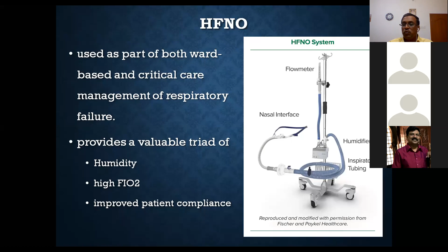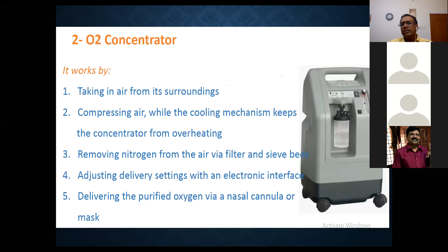This is an oxygen concentrator, not commonly used nowadays here, but it doesn't need any oxygen source. The oxygen source is the environment. It's taking air from the surroundings and compressing the air, and cooling mechanisms keep the concentrator from overheating, and it removes the nitrogen via filter sieve beds present here, thereby adjusting the delivery settings, and they can increase the concentration of oxygen that can be delivered to the patient. The FiO2 cannot be more than 50% by using this oxygen concentrator. Maximum oxygen concentration delivered is roughly 40 to 45%, maximum of 50% FiO2.